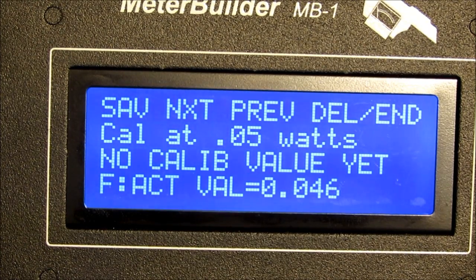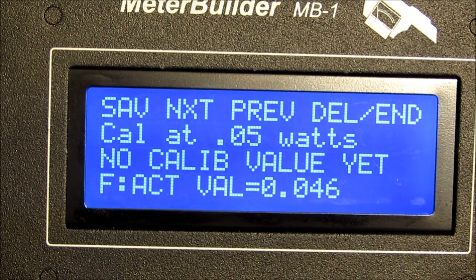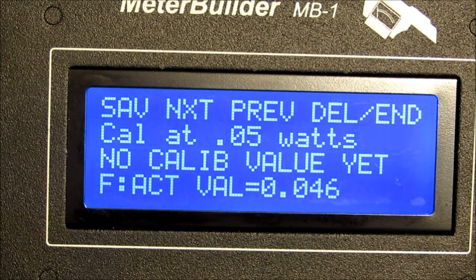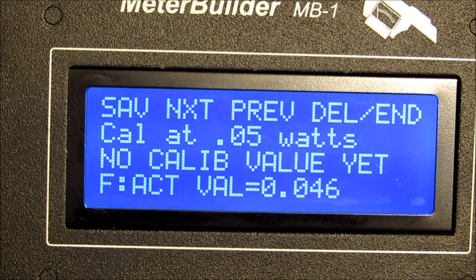If you're calibrating a coupler of unknown quality in terms of how closely it follows the ideal curve, start out with roughly 10 points, especially concentrating on the low power values, because that's where a lot of the couplers have a lot of difficulty. And after calibration, you can just run your calibrated meter against the reference that you use to calibrate it, and if it's in good shape, you're done. And if you see a couple of areas where the accuracy is not quite up to what your standards are, you can add additional points with the edit function.